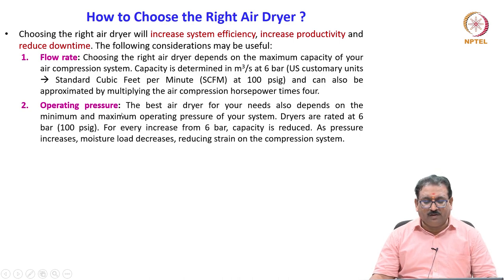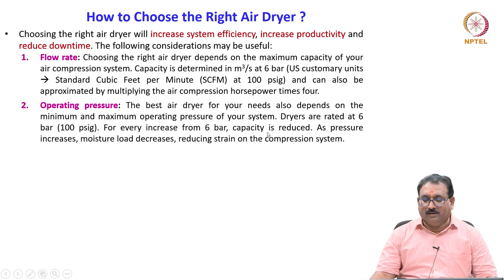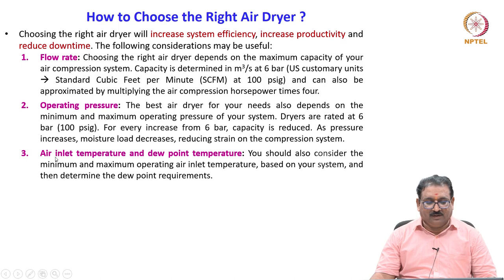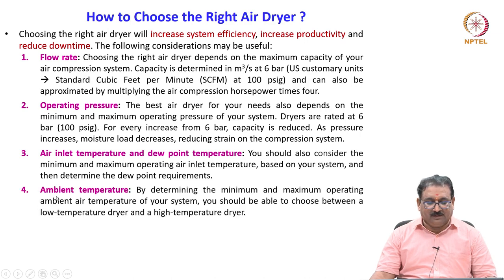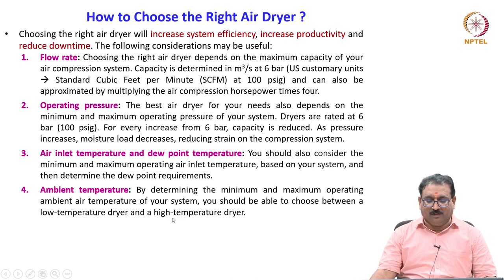Operating pressure is another consideration — the best air dryer also depends on the minimum and maximum operating pressure of your system. Dryers are rated at 6 bar. For every increase from 6 bar, capacity is reduced, but as pressure increases, moisture load decreases, reducing the strain on the compression system. The third parameter is air inlet temperature and dew point temperature. You should consider the minimum and maximum operating ambient air temperature and determine dew point requirements, choosing between a low temperature or high temperature dryer accordingly.